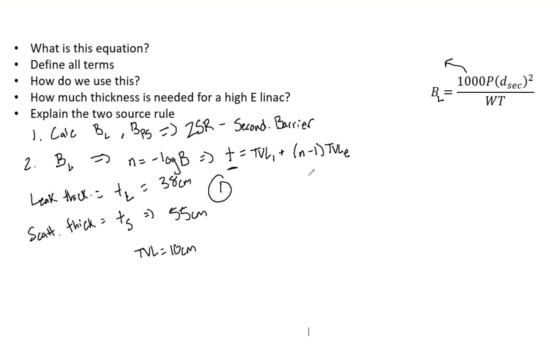The other option is if the thickness of the leakage, say is 50, and then the thickness of the scatter is 55 cm. Well, now they are only 5 cm different. The TVL is 10 cm. So now what we need to do is take the highest that we have. So we're going to do 55 cm. And we're going to add one HVL to that. And then that will incorporate and be strong enough to shield for both leakage and scatter.